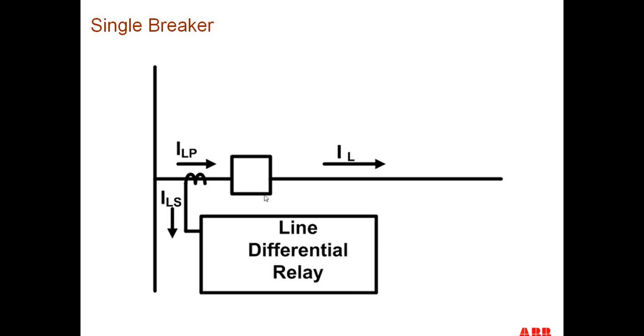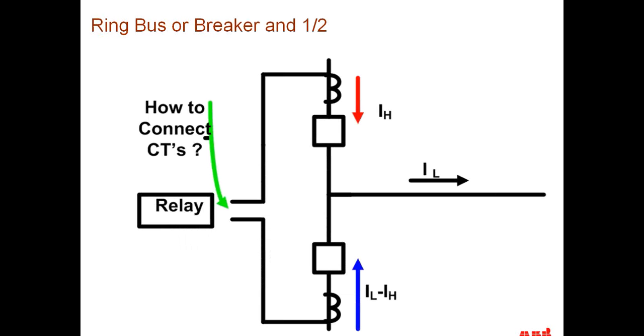So if we have a single breaker, remember we have information coming into a line differential relay, and a single breaker is very easy because the current going through this one CT is the same as the line current going out through the breaker. So we just have one connection between the CT and the line current differential relay. That's pretty straightforward.